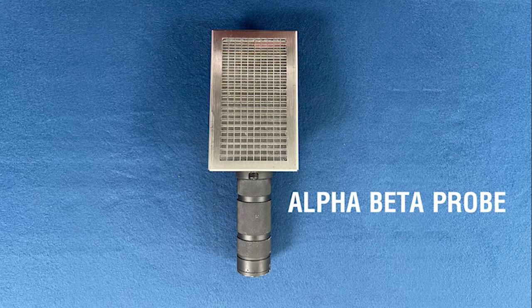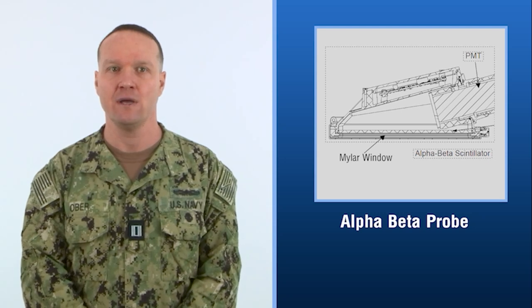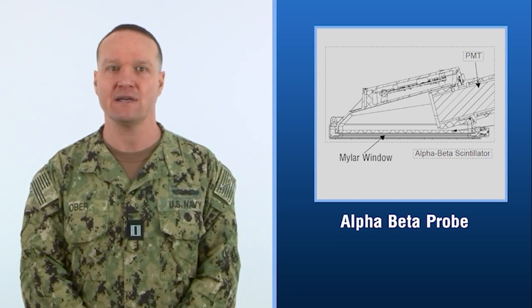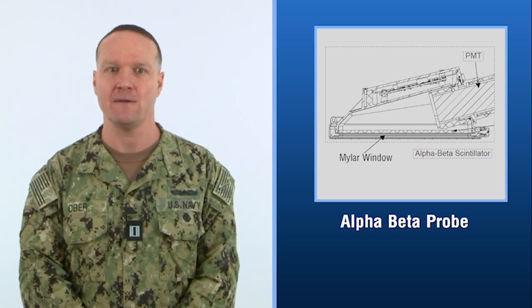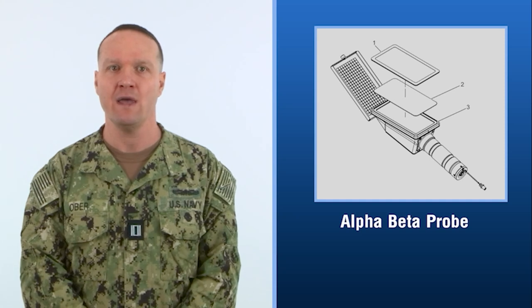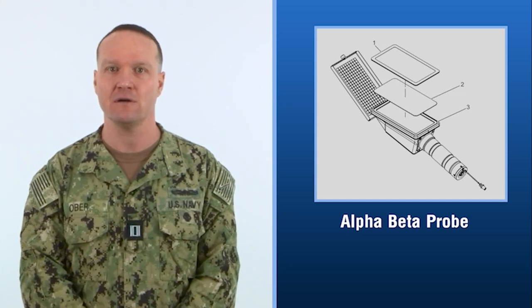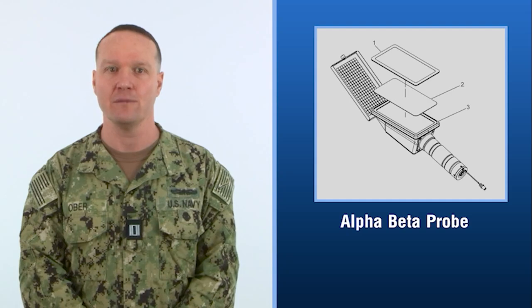Alpha-beta probe. The alpha-beta probe enables detection performance for both alpha and beta radiation with a single probe. The scintillator material is in close contact with a plastic light pipe that is attached to a photomultiplier tube, or PMT. A replaceable mylar window is used to cover the scintillation material and prevent light from entering the probe. If the mylar window is punctured, the detectors will be saturated with light and will not be able to accurately detect alpha and beta radiation.